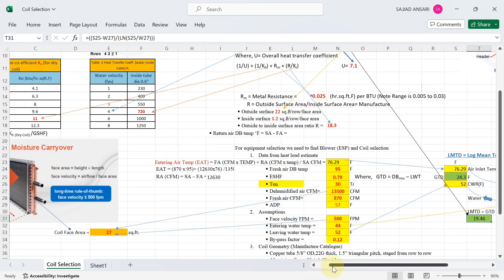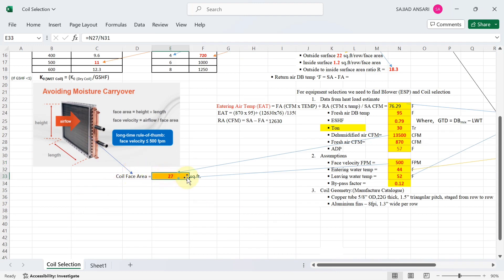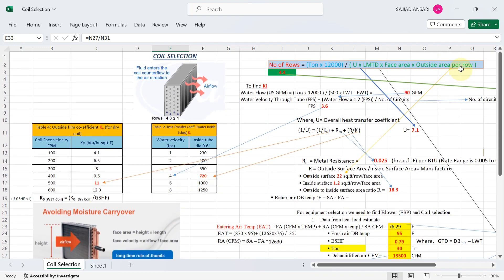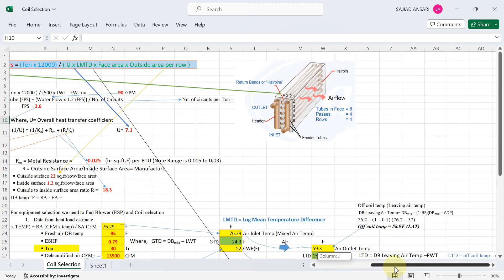Now let's calculate the face area of the coil. Face area = Dehumidify CFM ÷ Face velocity = 13,500 ÷ 500 = 27 square feet. Outside area per row from the manufacturer is 22 square feet per row per face area. Putting all values into the number-of-rows formula gives 4.4 rows.